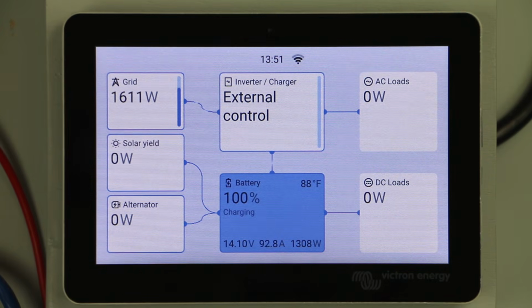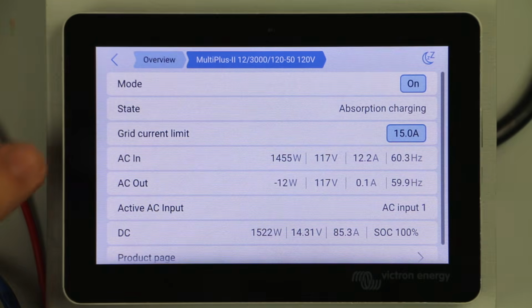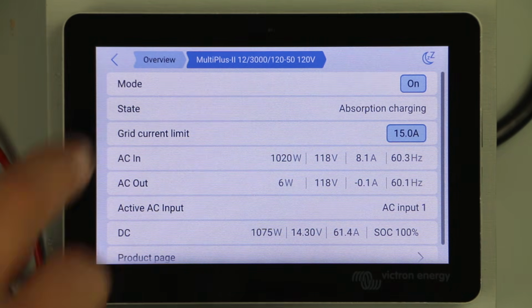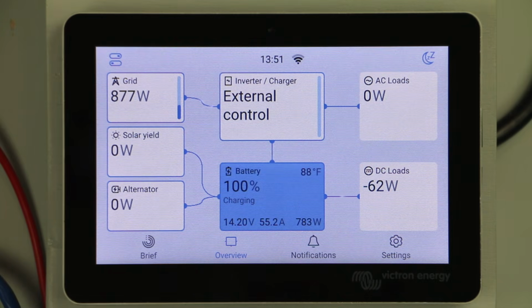All right, so we hit 100% and 14.2 volts. It looks like it's just about to hit 14.2. And we can check and see the state should change to absorption. So you can see it's now changed from bulk charging to absorption charging. We can hear the MultiPlus slow down. You can see the amperage start to slow down as the batteries fill up.